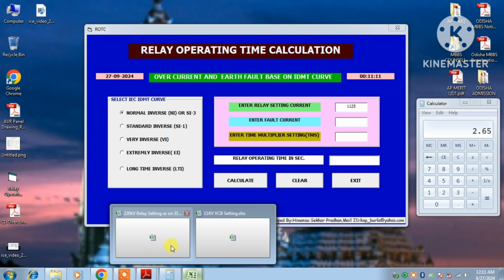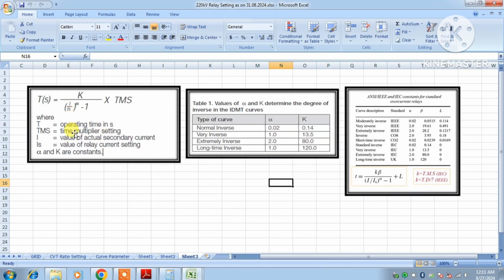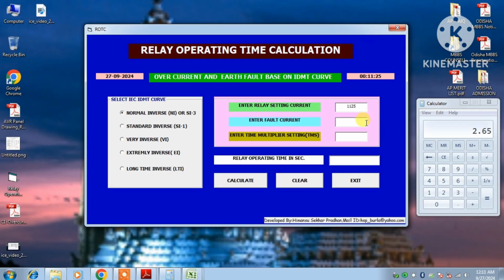As I described here, I by IS, where I is the fault current and IS is the setting current, or the relay current setting. So 1125 amps, and I will take suppose 6 times, 1125 into 6, that is 6750. My curve selection is SI1, and the TMS given is 0.37. To calculate it, it will operate in 619 milliseconds. So this is the utilization of this application.